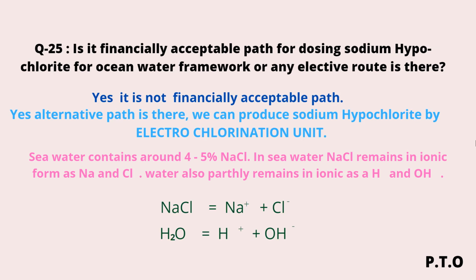Is it a financially acceptable path to dose sodium hypochlorite for the seawater system, or is there any alternative route? Yes, it is not a financially acceptable path. Yes, an alternative path is there. We can produce sodium hypochlorite by an electrochlorination unit.